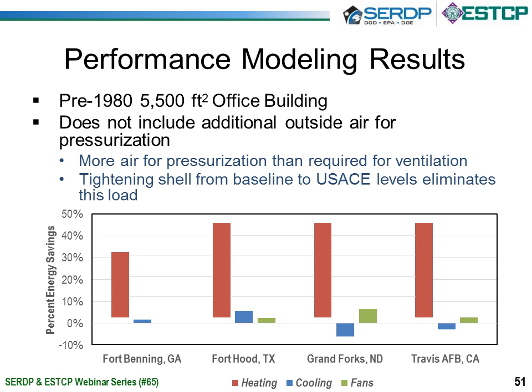But in drier climates like California and in the cool, dry North Dakota climate, extra infiltration into the building actually helps reduce the cooling load because there's a lot of cooling hours when outside air is cooler than inside air. So infiltration in those cases actually helped the cooling load in those buildings. So there's also a little bit of fan energy savings. It looks like this plot didn't come in very clear, but in Fort Benning there was also some fan energy savings. That's basically just reduced fan energy because there's less heating requirements for the building.